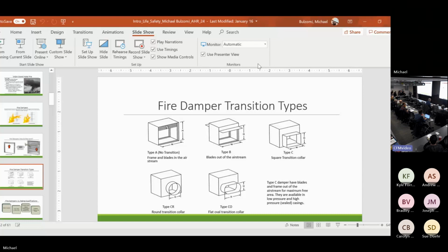Because now when I have a multi-section, if it's 2 sections wide and I put this transition, the frame members on the inside of the dampers are still going to be in the airstream. So putting a transition on a multi-section damper does nothing for pressure loss. But this would be 100% free area on a single section. We most commonly see these round ones not being used for pressure loss, but because there's true round ductwork, and this is what we're choosing to put through there. There are other options. I already showed you.